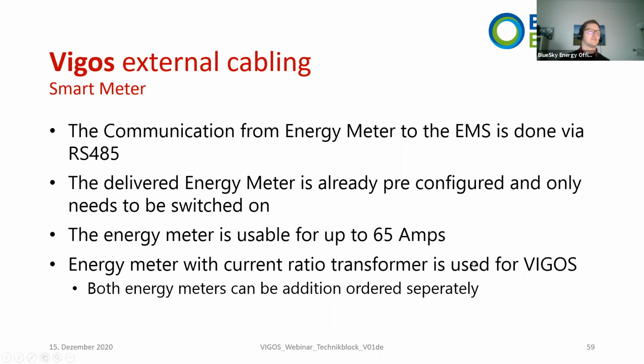After that, you can also do the energy meter cabling. The communication is done via RS485 from the EMS to the energy meter. So that's really an important connection you have to do. The energy meter itself is delivered already pre-configured and only needs to be switched on or needs to be cabled.